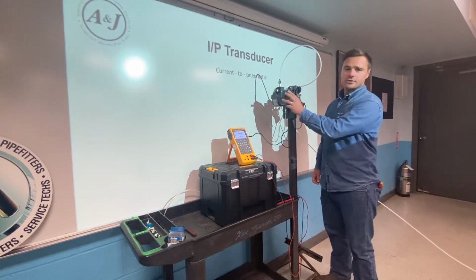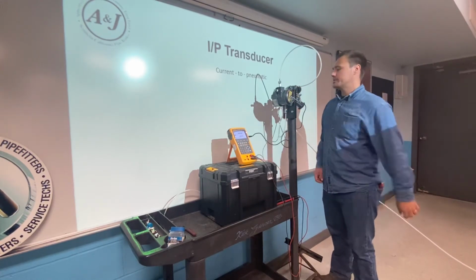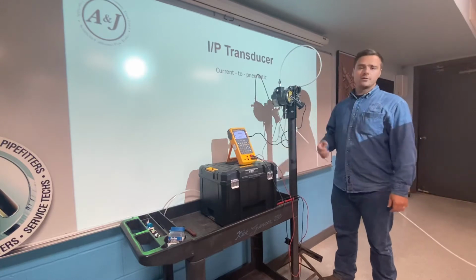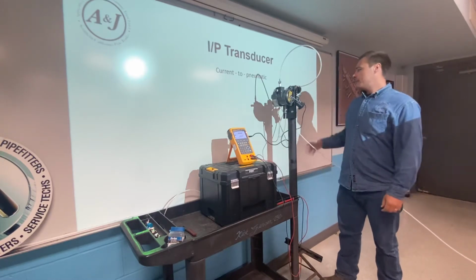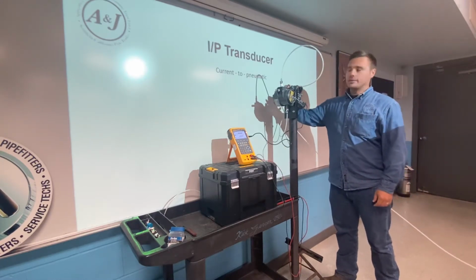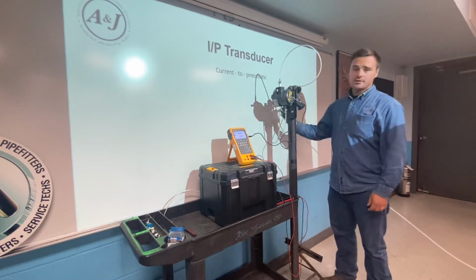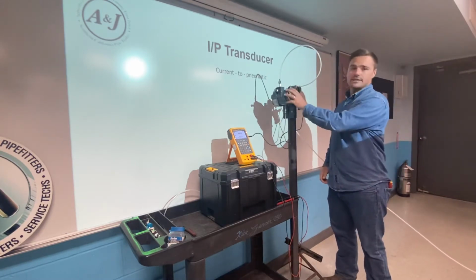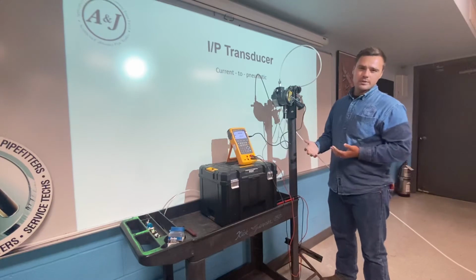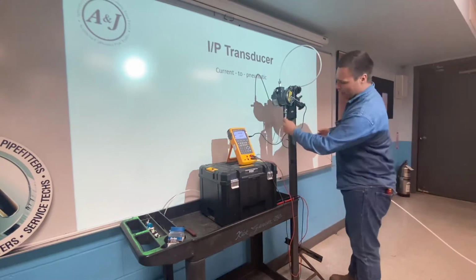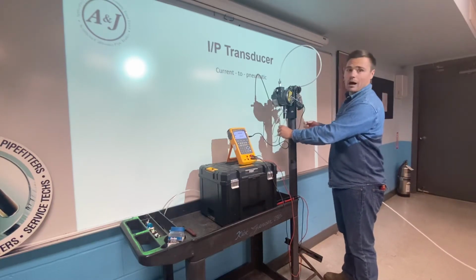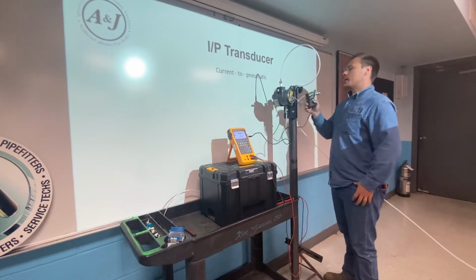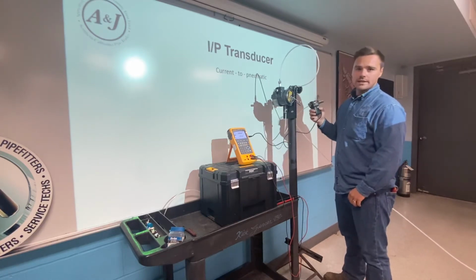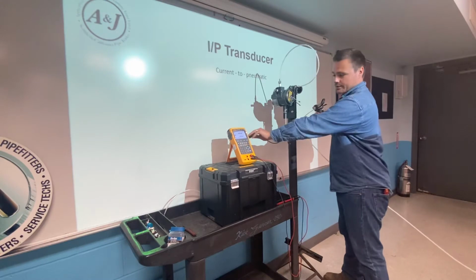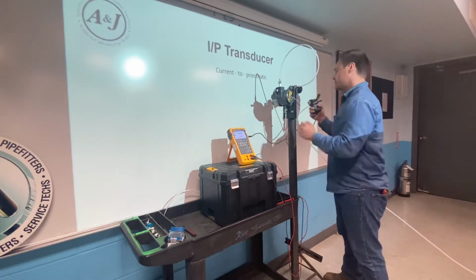What we have here is a Fisher Model 846 I2P transducer. Like we already stated from our schematic drawing, we have an instrument air supply coming into our regulator right here, which drops down our pressure to a usable pressure that doesn't damage the device, set to about 20 psi. Coming out of the output, we have our pressure module, which reads the output signal of the I2P and converts it to a digital signal, which is read by our Fluke.